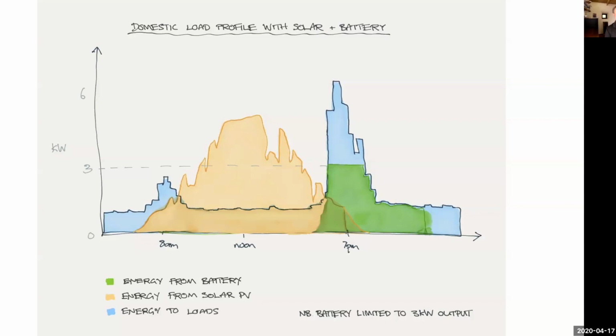In the evening, we've got a load that comes on, and I've shown here that the battery energy cuts out at 3 kilowatts. Now, this would mean you would need a generator, because if your loads go to 6 kilowatts but your inverter can only deliver 3, you're going to have a generator set to parallel with it. So whether it's paralleling or it switches over, that's another option. It's not so common anymore, but in the day when I first went off-grid back in 1991, we just basically had a changeover switch. We'd turn the house over to generator only or inverter only. But because of modern power electronics, it's now possible to parallel that inverter with the generating set.